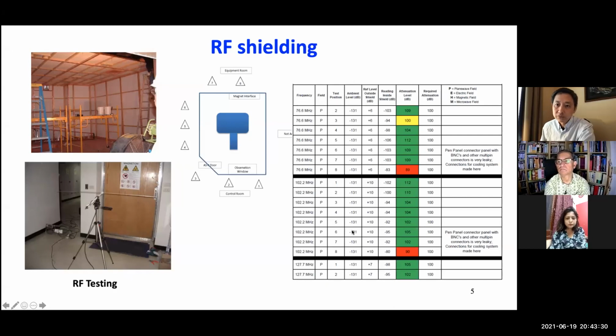So this is just a part of a report. I'm trying to show you we are testing different frequencies. Sorry, the font size is probably small, but it's just the idea. This is about 70 megahertz. That's 100 megahertz. This is 128 megahertz. For 1.5T, at least we need to test the 1.5T central frequency, which is 64 megahertz, plus higher frequencies, usually more than 100 megahertz. For 3T, we want to make sure to test up to the 3T central frequency, which is 128 megahertz, plus higher, around 150 megahertz.